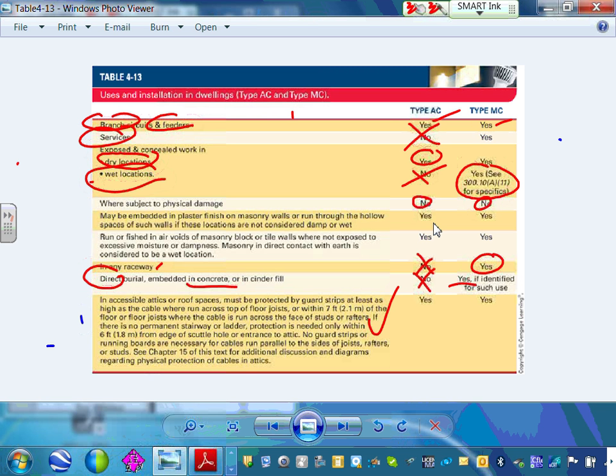So that's why, if you're above ground like here, they typically use EMT conduit with compression fittings. The compression fittings are watertight. Okay. Now on the roof, this one also will get you the EMT with the compression fitting. So that's why EMT also in a wet location above ground will work.